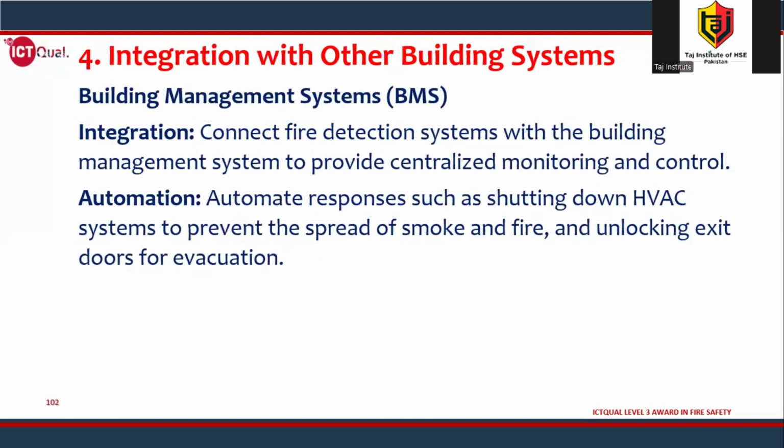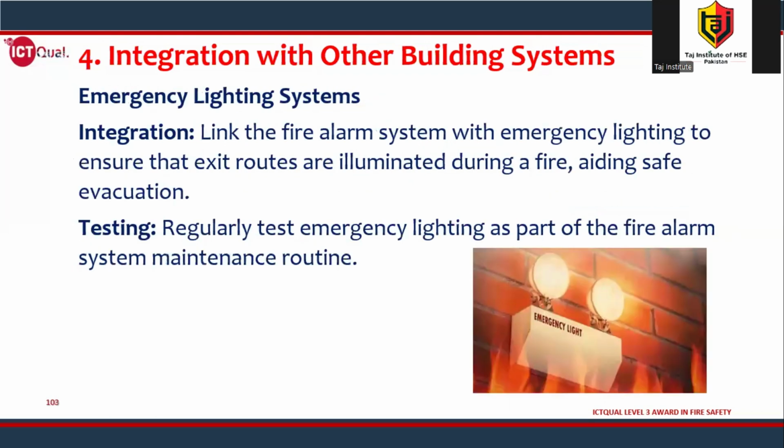Building management systems, BMS. BMS means building management system. Integration. Connect fire detection systems with the building management system to provide centralized monitoring and control. Automation. Automate responses such as shutting down HVAC systems to prevent the spread of smoke and fire, and unlocking exit doors for evacuation.